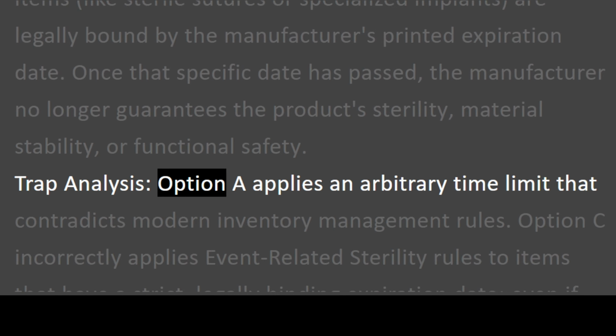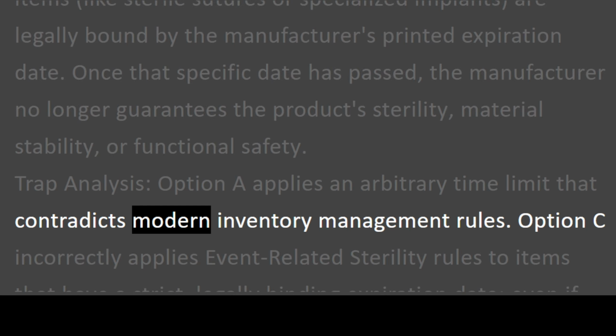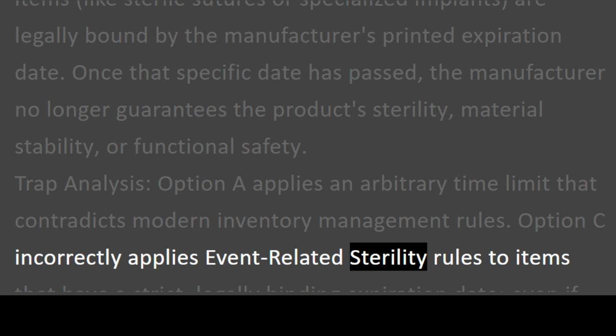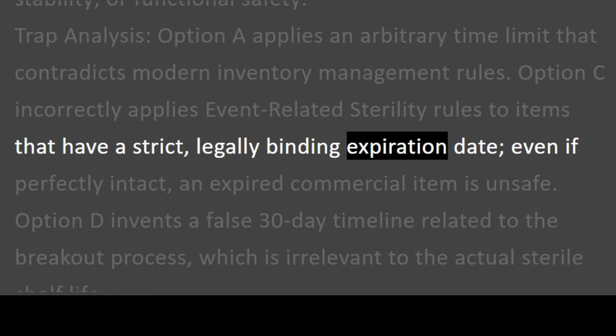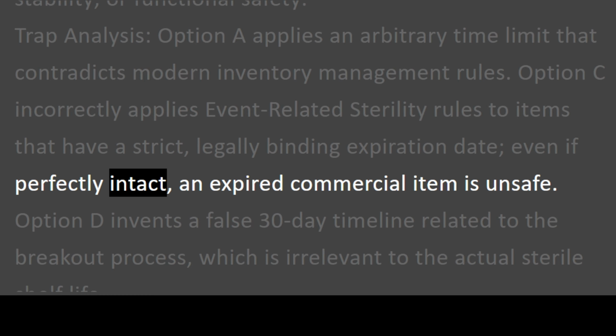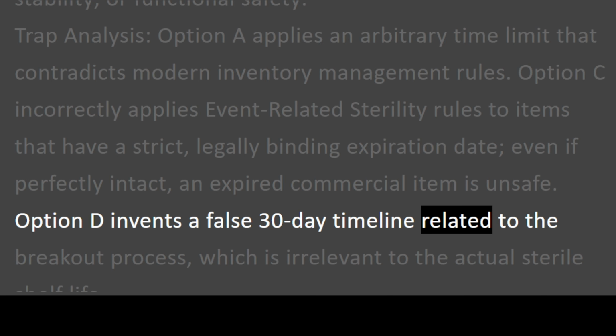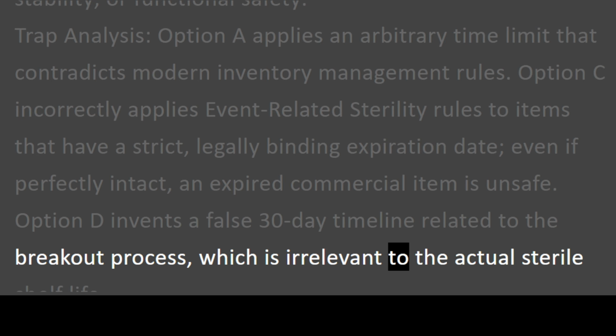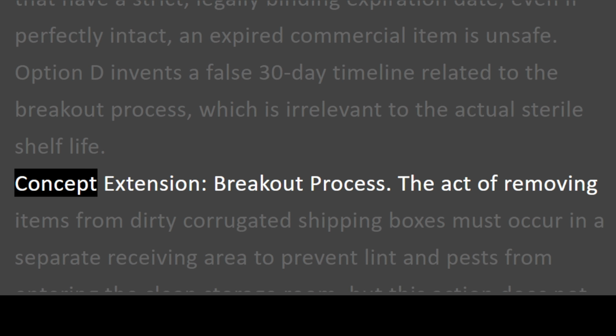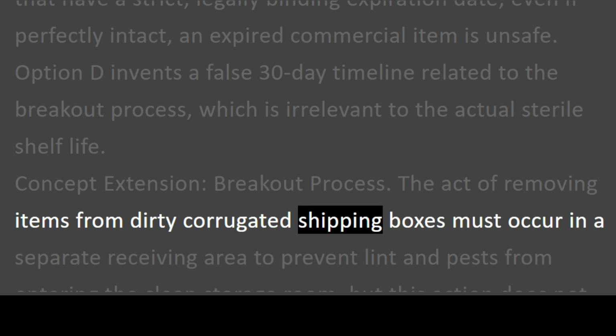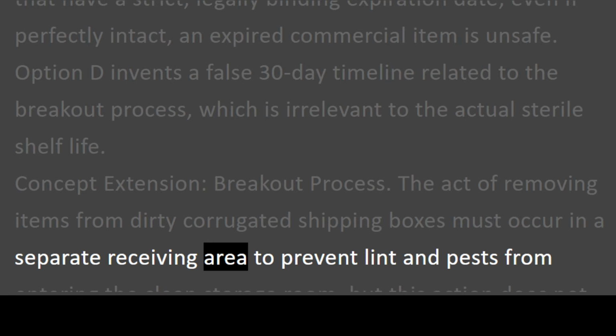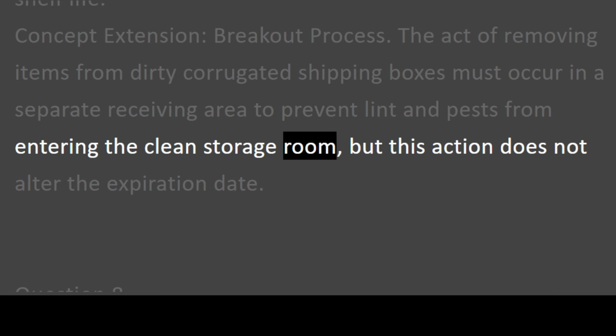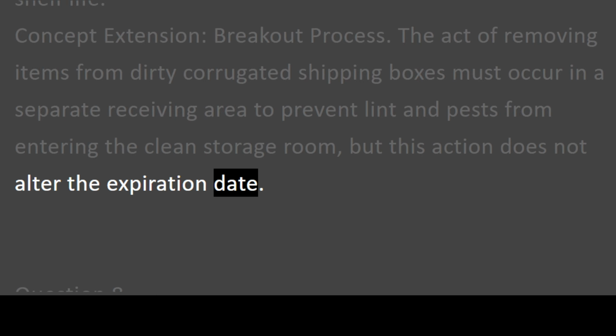Trap analysis. Option A applies an arbitrary time limit that contradicts modern inventory management rules. Option C incorrectly applies event-related sterility rules to items that have a strict, legally binding expiration date. Even if perfectly intact, an expired commercial item is unsafe. Option D invents a false 30-day timeline related to the breakout process, which is irrelevant to the actual sterile shelf life. Concept extension, breakout process. The act of removing items from dirty corrugated shipping boxes must occur in a separate receiving area to prevent lint and pests from entering the clean storage room, but this action does not alter the expiration date.